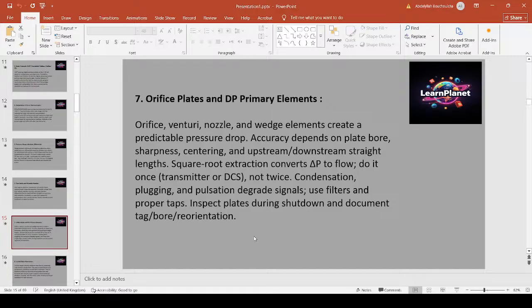Orifice plates and DP primary elements. Orifice, venturi, nozzle, and wedge elements create a predictable pressure drop. Accuracy depends on plate bore, sharpness, centering, and upstream-downstream straight length. Square root extraction converts delta P to flow. Do it once, in the transmitter or DCS, not twice. Condensation, plugging, and pulsation degrade signals. Use filters and proper taps. Inspect plates during shutdown and document tag, bore, and orientation.